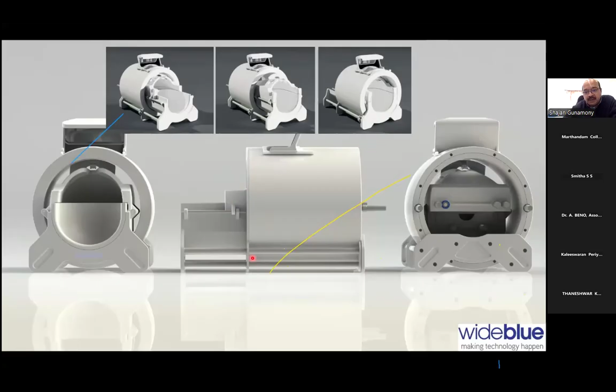We also implemented this sliding mechanism, which means that the receiver is split in 2 halves. The patient will lie on the bottom, the posterior half, then we close the anterior half. So that's the final scan position. At some point during this project, we decided to go to a 64 channel design because, as I said earlier, the 7 Tesla Siemens scanner has 64 channels, whereas the current industry standard has only 32 channels. So we decided to go for a 64 channel coil.